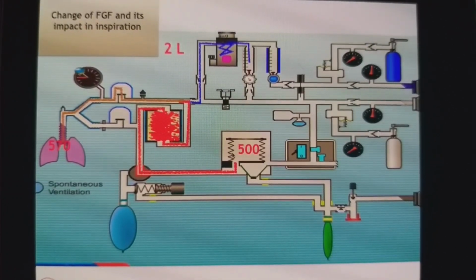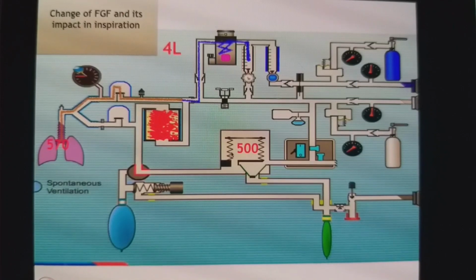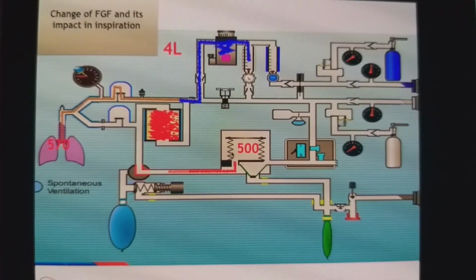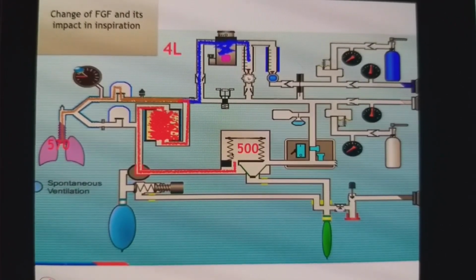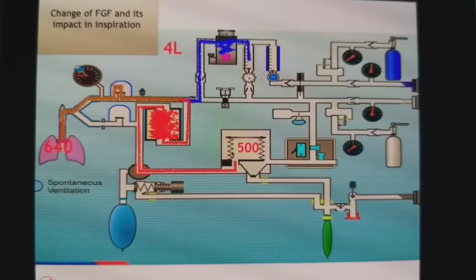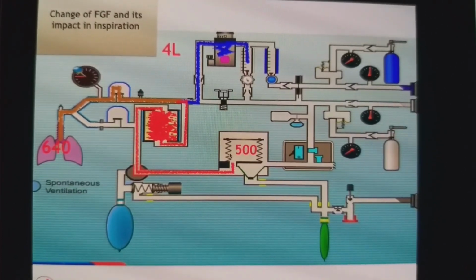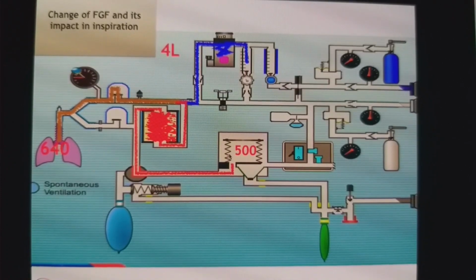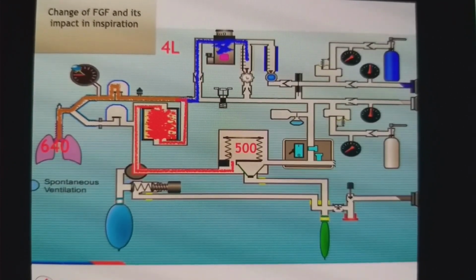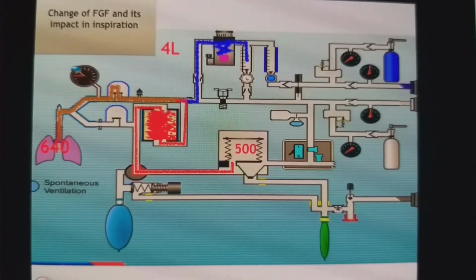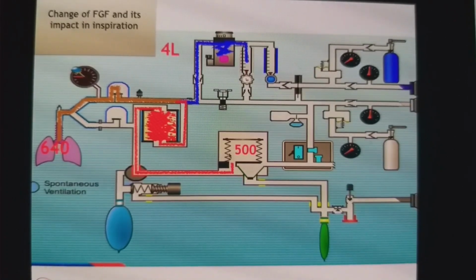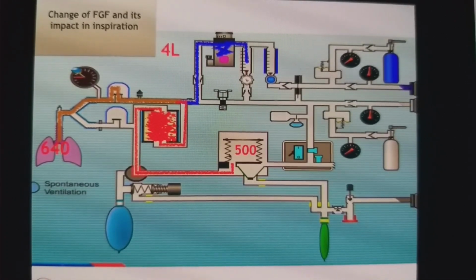The patient may receive 570 ml. But imagine if you increase the flow from 2 liters to 4 liters, a greater amount of flow is joining in the inspiratory line, and the tidal volume will be 640. So in this situation, where fresh gas flow is joining with the ventilator flow in the inspiratory line, the tidal volume may vary if you change the fresh gas flow.